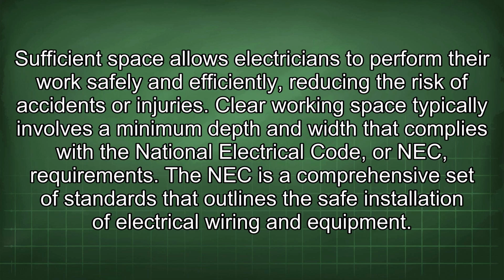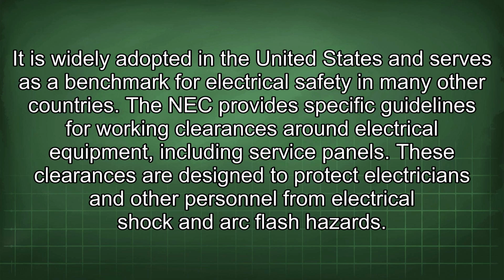Clear working space should be provided in front of the panel board for servicing and maintenance. Sufficient space allows electricians to perform their work safely and efficiently, reducing the risk of accidents or injuries. Clear working space typically involves a minimum depth and width that complies with the National Electrical Code, or NEC, requirements. The NEC is a comprehensive set of standards that outlines the safe installation of electrical wiring and equipment. It is widely adopted in the United States and serves as a benchmark for electrical safety in many other countries. The NEC provides specific guidelines for working clearances around electrical equipment, including service panels. These clearances are designed to protect electricians and other personnel from electrical shock and arc flash hazards.